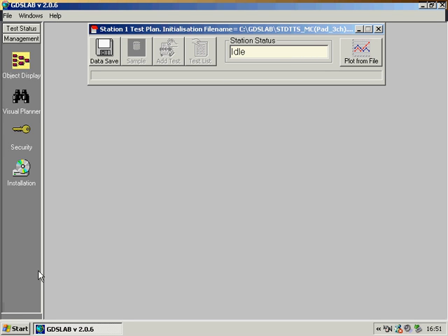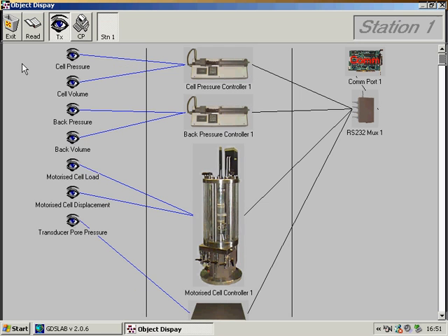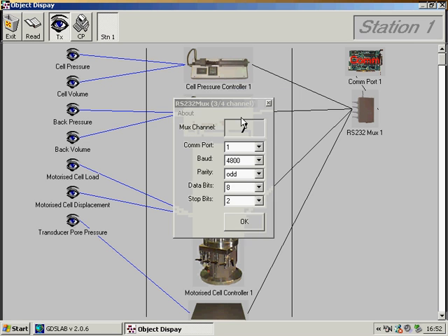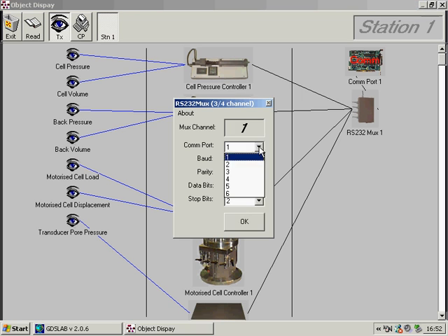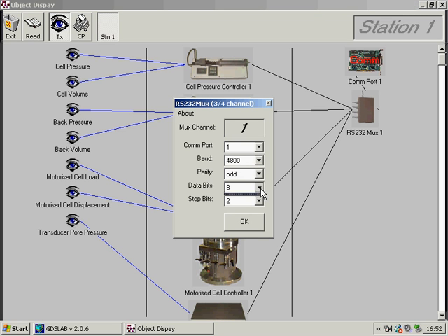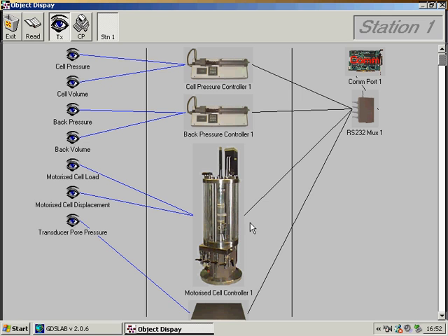Now I go back to the object display from the management. Not only does the object display help us diagnose any system problems, it allows us to set up the devices for communication parameters and calibrations. By clicking on the actual device here, comms parameters may be set according to the device requirements.